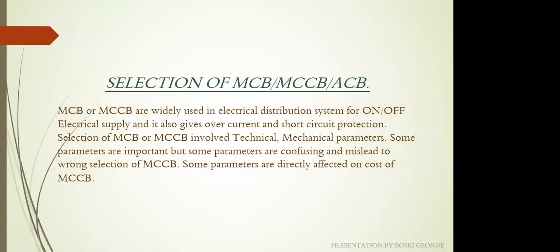The main part is selection of switchgears: MCB, MCCB, or ACB, and how we select them. The electrical switchgear we use has basic protection against overcurrent and short circuit mainly, but some clients may ask for more protection, like undervoltage protection. In that case you have to select an MCCB with all these protection classes, as per the application of the panel, so we can select switchgears according to the needs of the client, the end users.